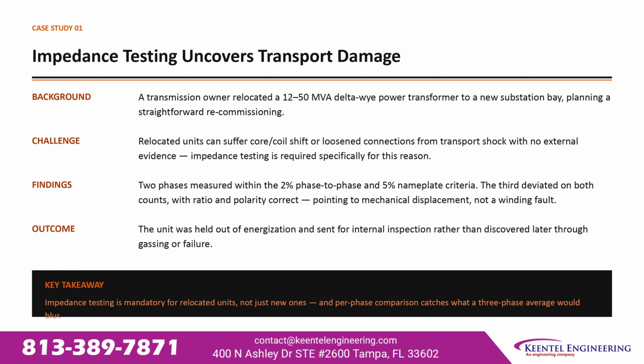A transmission owner relocated a 12 to 50 megavolt amperes delta Y power transformer to a new substation bay, planning a straightforward recommissioning. The challenge: relocated units can suffer core or coil shift or loosened connections from transport shock with no external evidence at all, which is exactly why impedance testing is required.